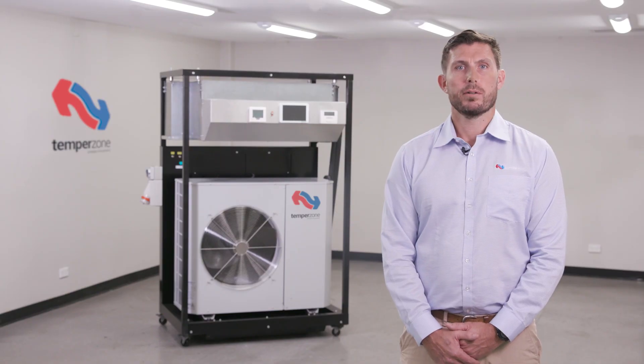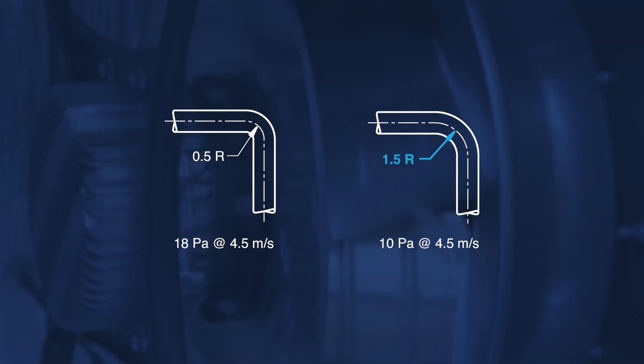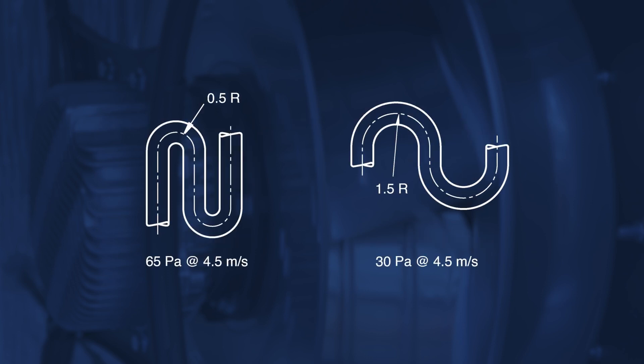Maximum airspeed across the indoor coil should not exceed 1.3 meters per second. Use radii of at least 1.5 times the duct diameter for bends. Tight radii bends can double the pressure loss. 180 degree U-bends surprisingly do not generate double the pressure loss of a 90 degree bend, but something much less than double.